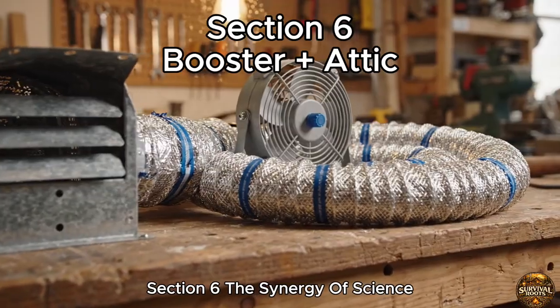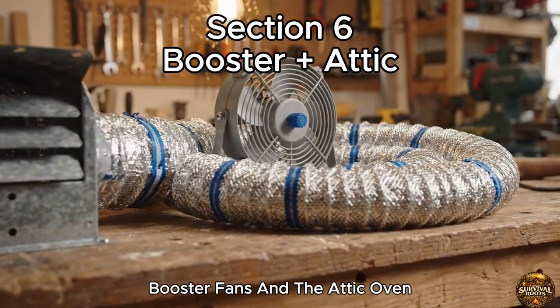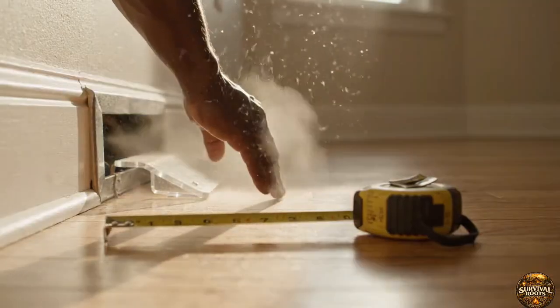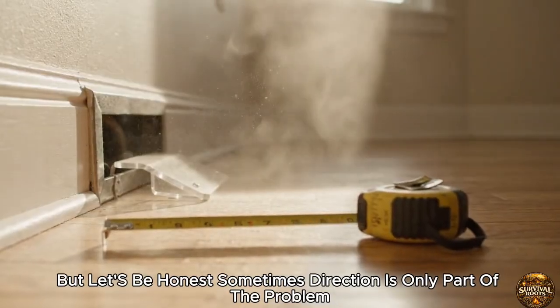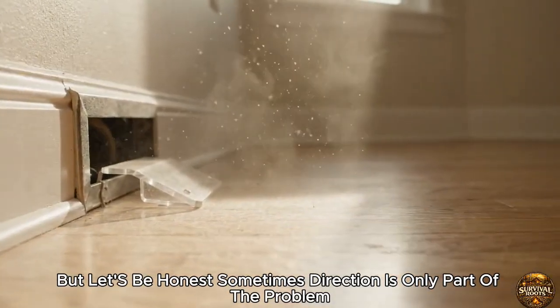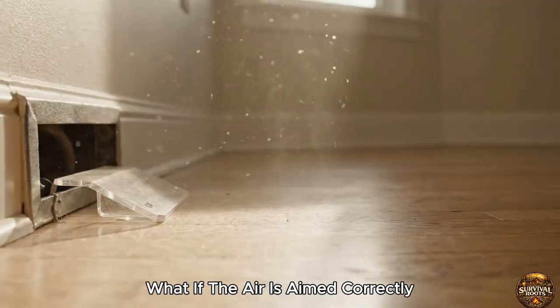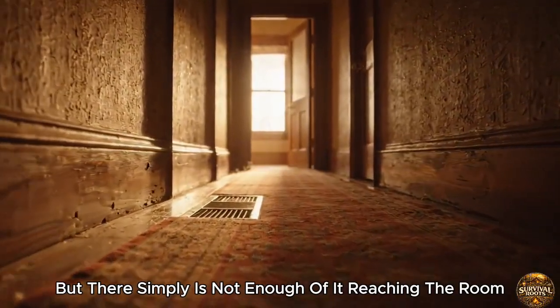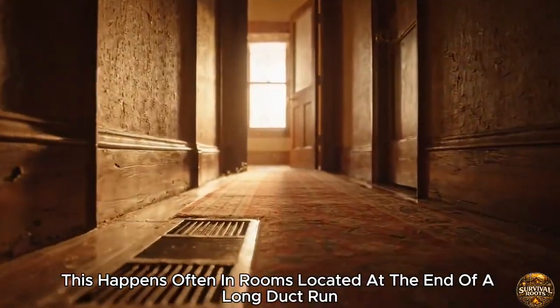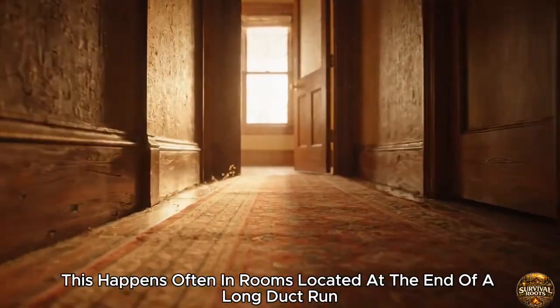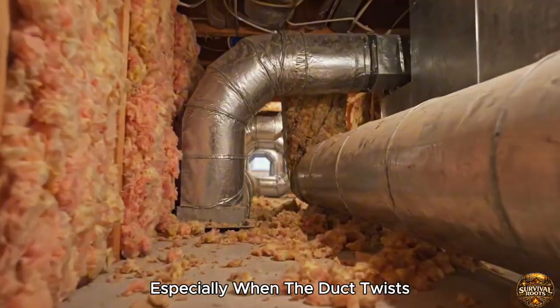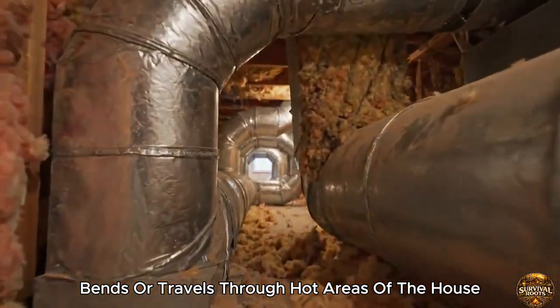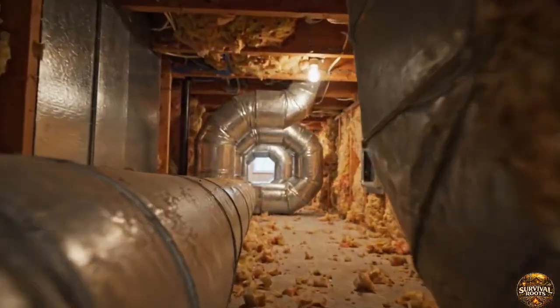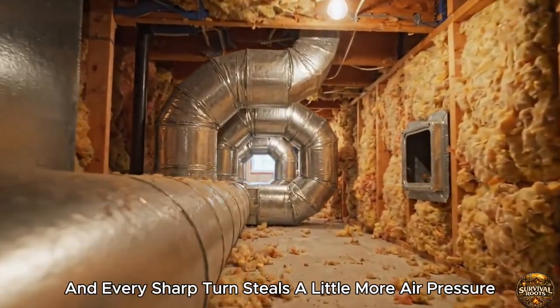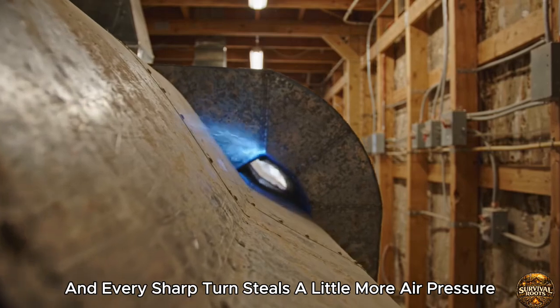Section 6, the synergy of science, booster fans, and the attic oven. But let's be honest. Sometimes direction is only part of the problem. What if the air is aimed correctly, but there simply is not enough of it reaching the room? This happens often in rooms located at the end of a long duct run, especially when the duct twists, bends, or travels through hot areas of the house. Every foot of ductwork and every sharp turn steals a little more air pressure.